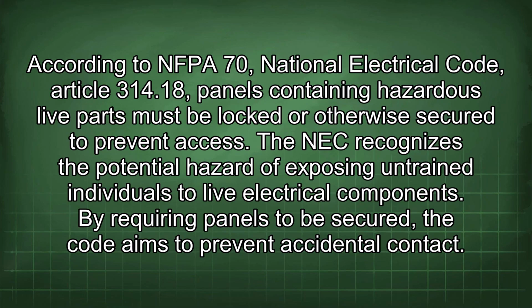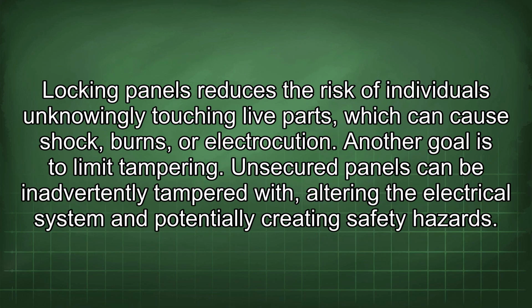According to NFPA 70, National Electrical Code, Article 314.18, panels containing hazardous live parts must be locked or otherwise secured to prevent access. The NEC recognizes the potential hazard of exposing untrained individuals to live electrical components. By requiring panels to be secured, the code aims to prevent accidental contact.